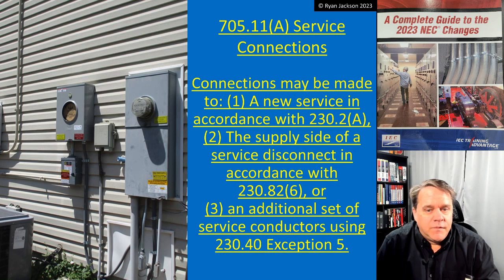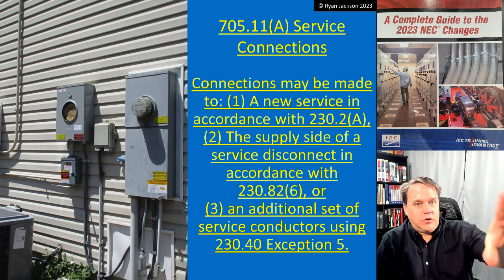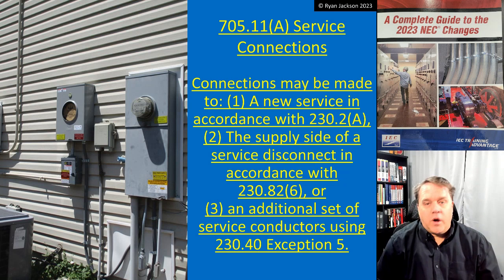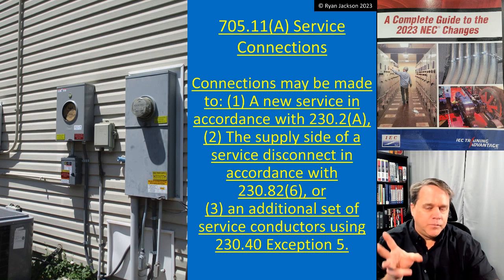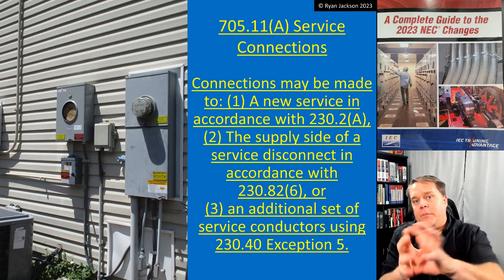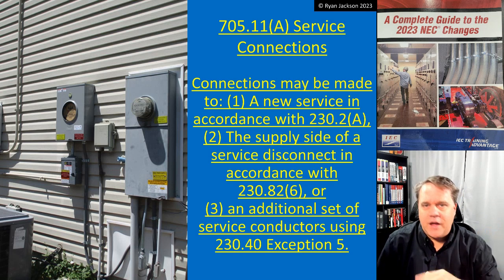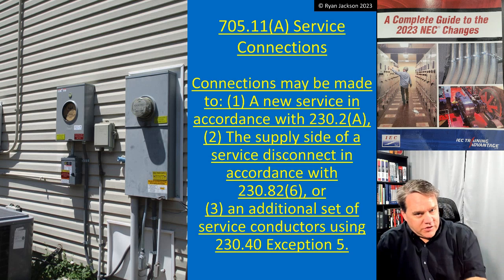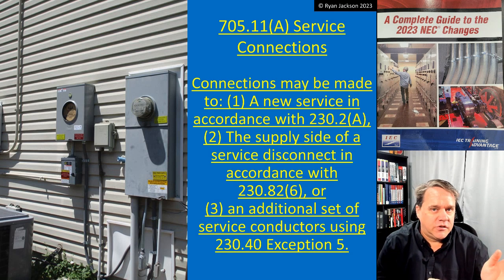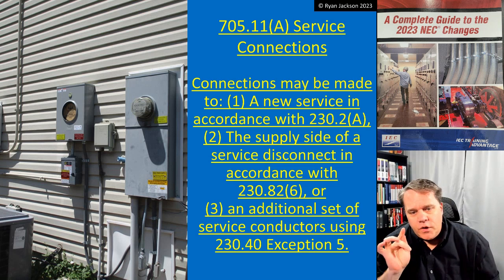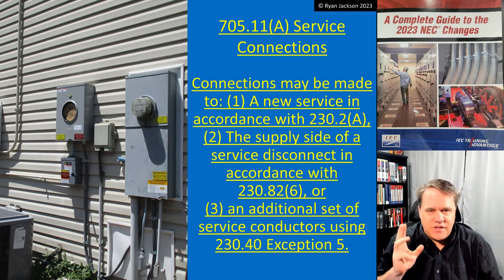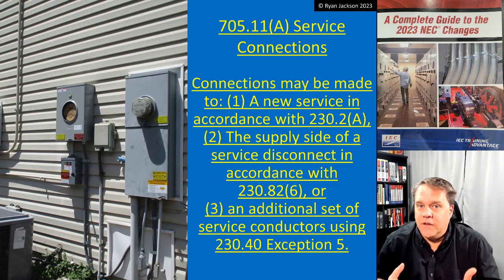Connections may be made to a new service in accordance with 230.2(A), so you create a new service for your interconnect system; or on the supply side of a service disconnect in accordance with 230.82 item 6, which is one of the permitted things you can do upstream of the service. 230.82 gives a list of about 10 items saying nothing can be installed upstream of the service disconnect except those items — and one of them is an interconnected power production source. Or you can use an additional set of service conductors using 230.40 Exception No. 5. Article 705 is by its nature somewhat complex.